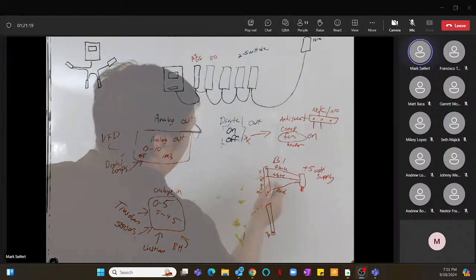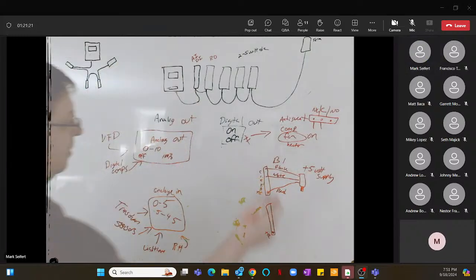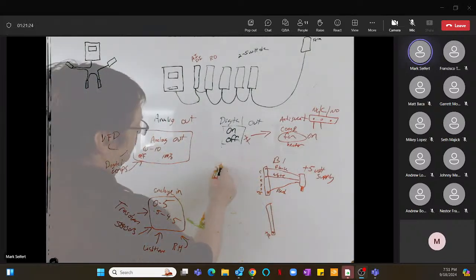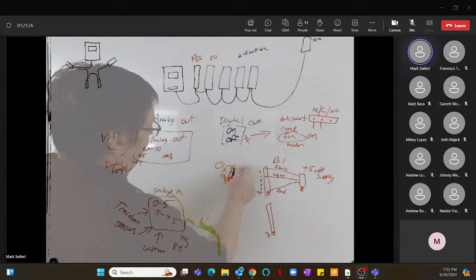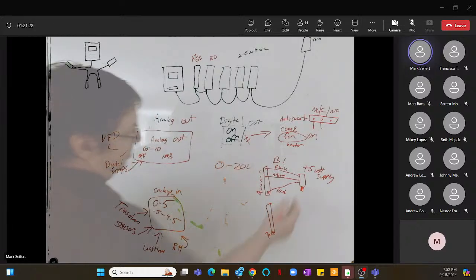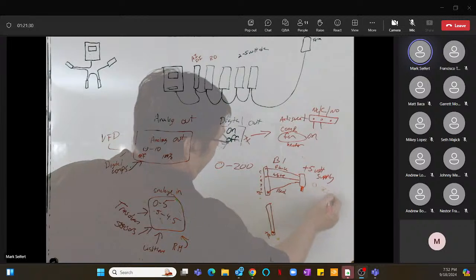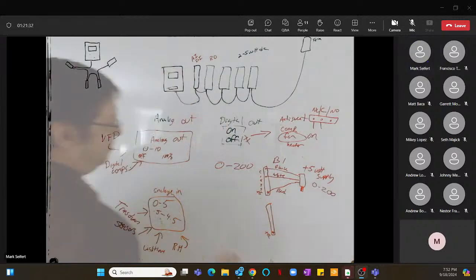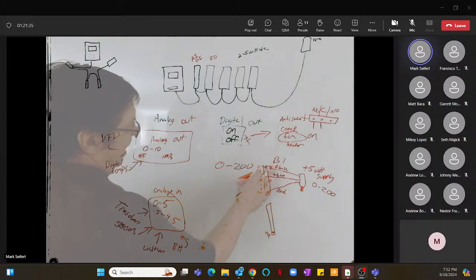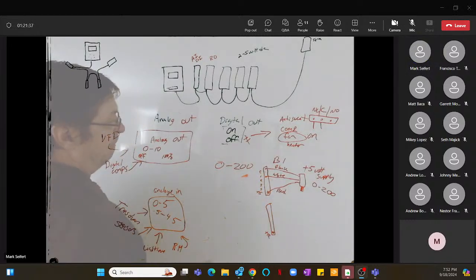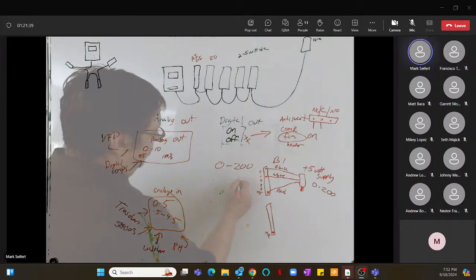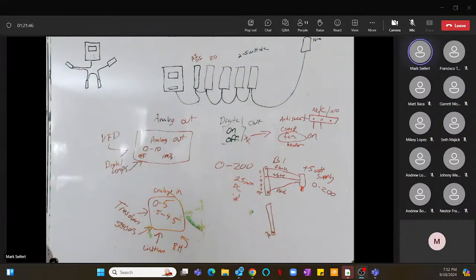If you want to check how accurate it is, let's say you've got a 0 to 200 transducer right here, 0 to 200. You check between black and white, and you have 2.5 volts DC. What do you suppose your pressure should read? This should be an easy one, because it's easy for me, and I'm not good at math.